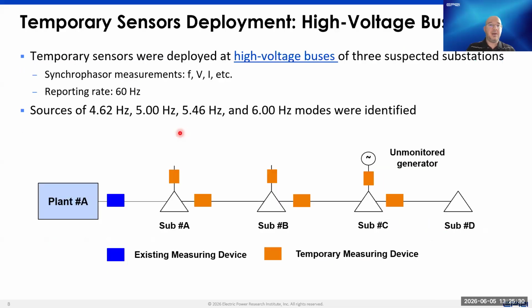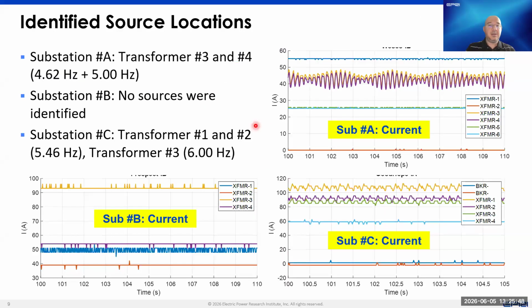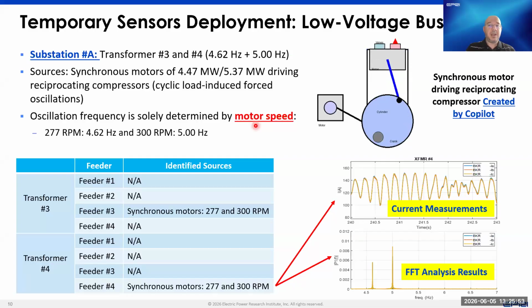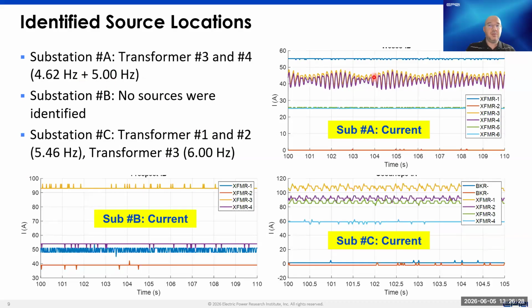So if I go back and show you all the frequency ranges of the oscillations that we were seeing across the system, we were seeing oscillations at 4.62, 5, 5.46, and 6 hertz. At that point we were successful in indicating that the motors are the ones creating those oscillations, and the frequency of the oscillations is correlated with, or dependent on, the nominal speed of those motors in RPM. So you see again in substation A, they had motors with 277 and 300 RPM. This is where the 4.62 and 5 hertz oscillations were coming from. And we were able to see those when analyzing the PMU data with a simple FFT.